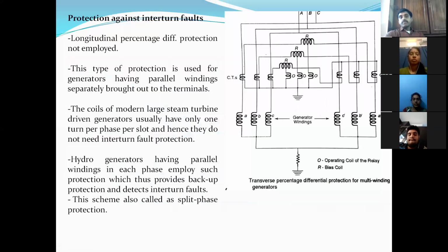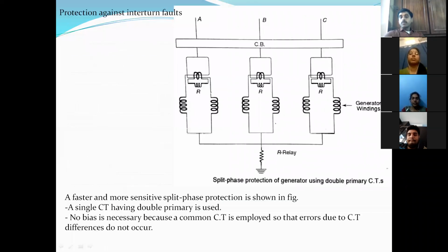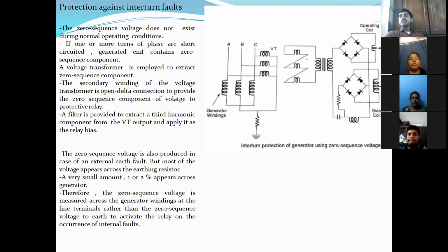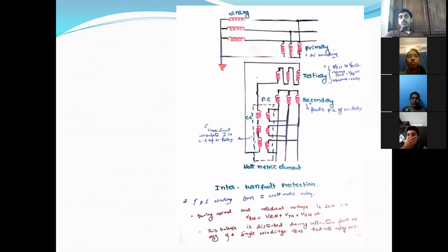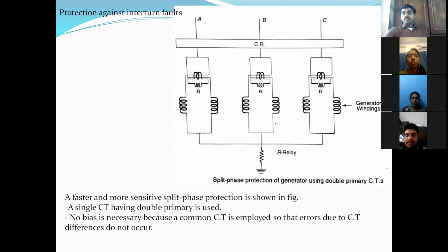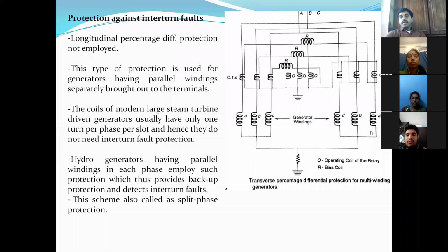To protect the generator against interturn faults, we have different schemes: transverse percentage differential scheme and split phase protection scheme, as well as zero sequence voltage protection and the wattmetric relay. We'll discuss these four. First, see here, longitudinal percentage differential protection is not employed. Previously, I have seen LG faults, LL faults. The longitudinal normal differential protection is not used for interturn faults.